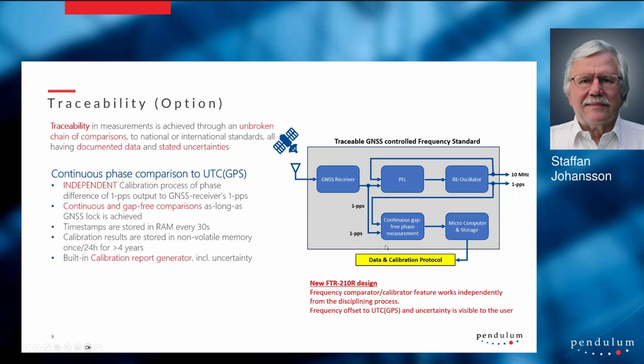Because we have a separate and independent comparator that compares the 1 PPS from the GNSS with the 1 PPS output from our Rubidium. It calculates parameters like average time offset, average frequency offset, etc., and produces a calibration protocol with the data. We store the timestamps every 30 seconds in RAM, and we store the calibration results over 24 hours, once a day at midnight, in a flash memory. And we have the built-in calibration report generator.